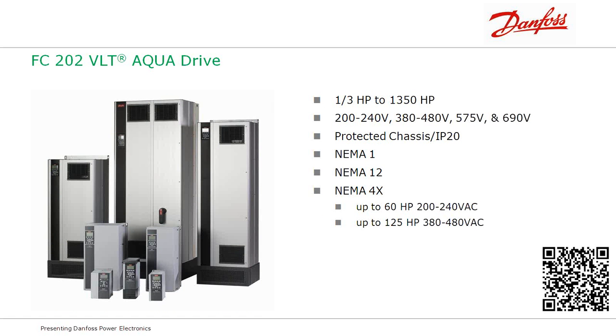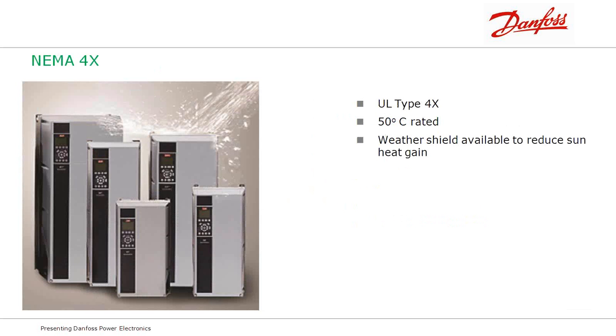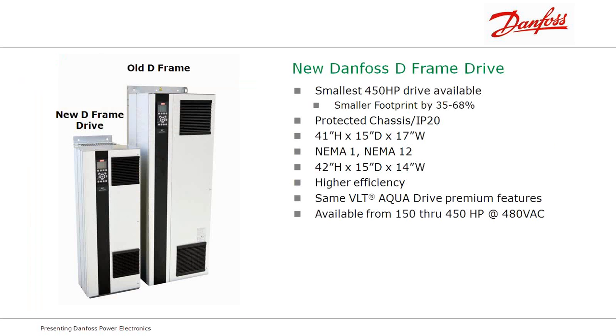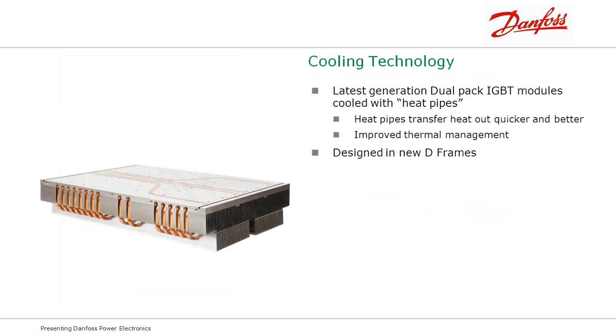Some of the things we're looking at here on the screen with the Aqua product series, a very extensive product line from a fractional horsepower to 1,300 horsepower with a variety of the voltages available throughout the world. Also enclosure ratings, some of the newer things we're promoting is a NEMA 4X rating of the units, 50 degrees C, 122 degrees Fahrenheit, allows you to mount the drive outside where it needs to be, not necessarily where it has to be.